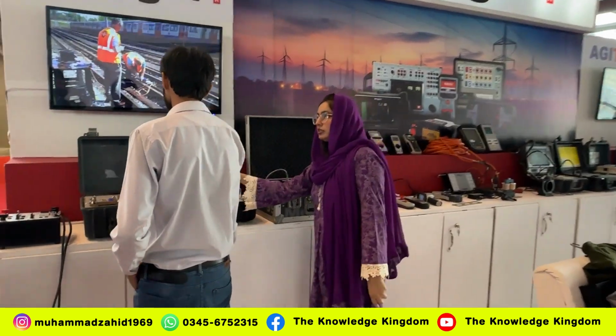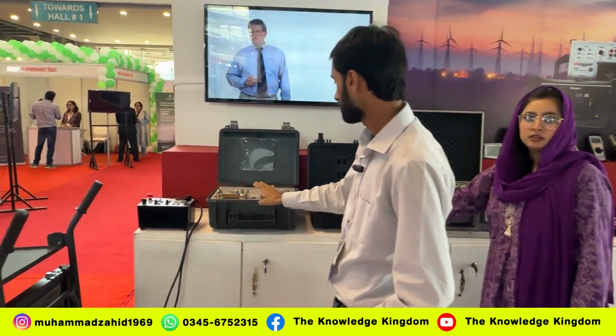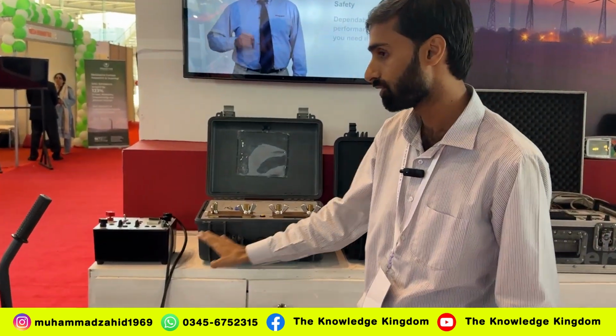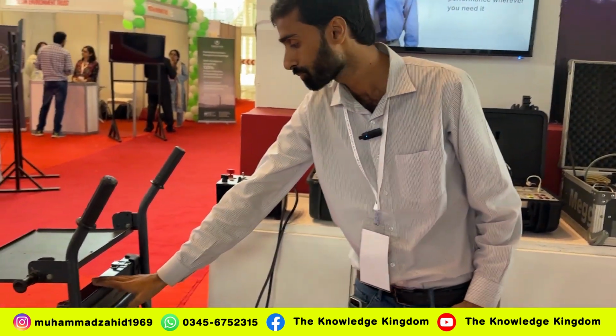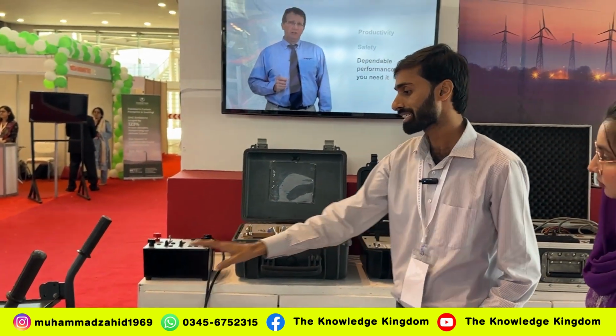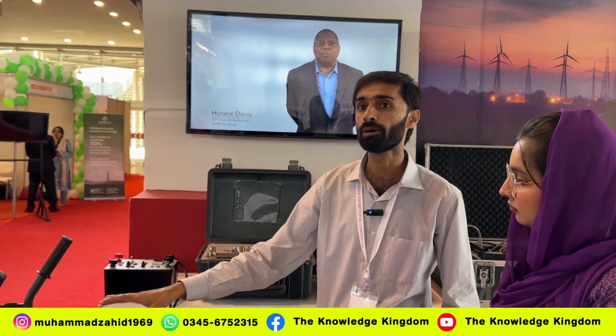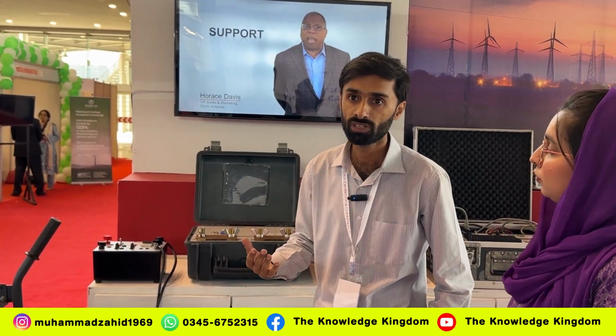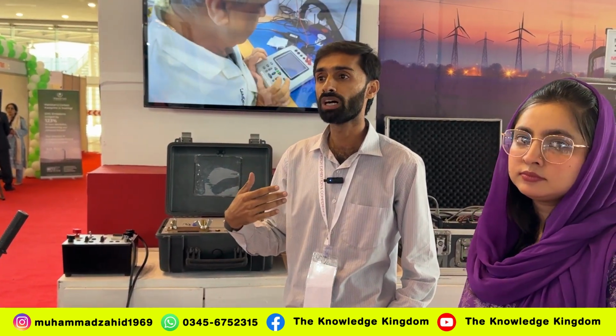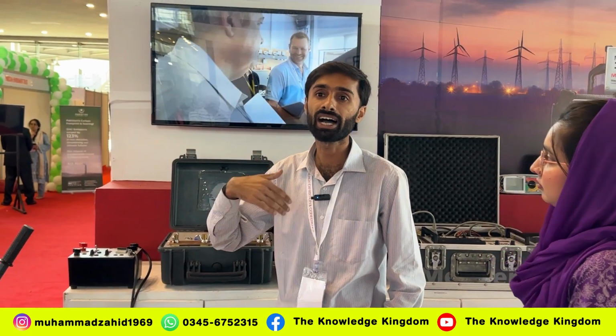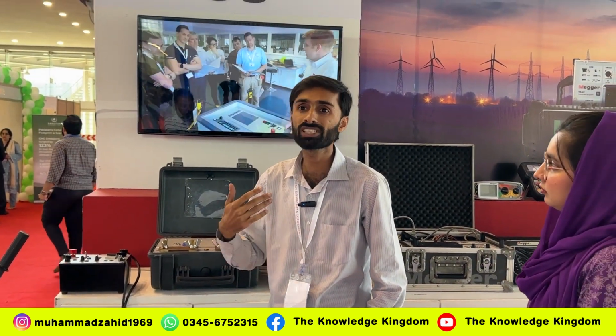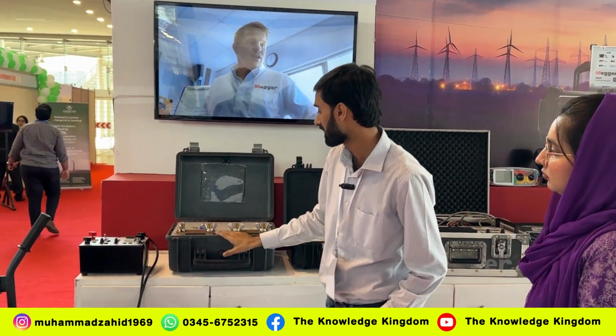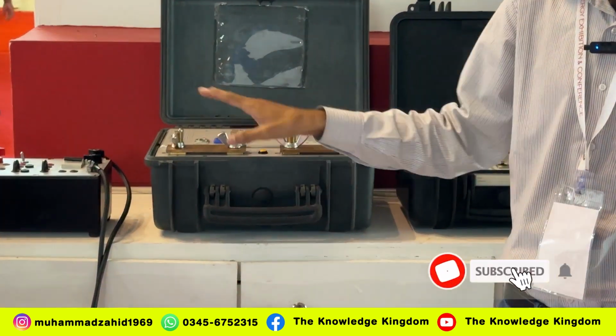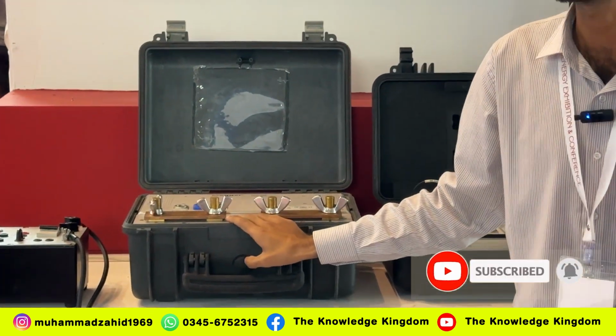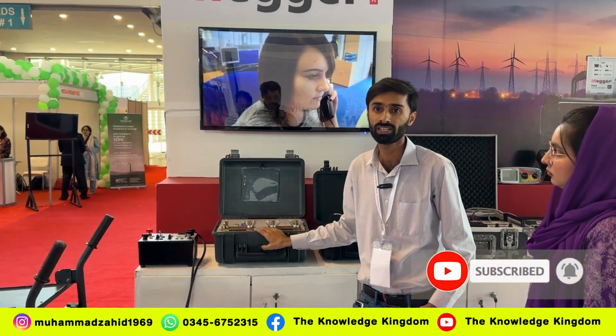Coming toward this, or has this been explained? This equipment is part of our TRAX system. Basically, TRAX itself can provide the current up to 800 amps. But if you want to get a higher range, like to do the scheme verification, this equipment can be connected as a separate accessory, and with this it can provide the current up to 2000 amperes.